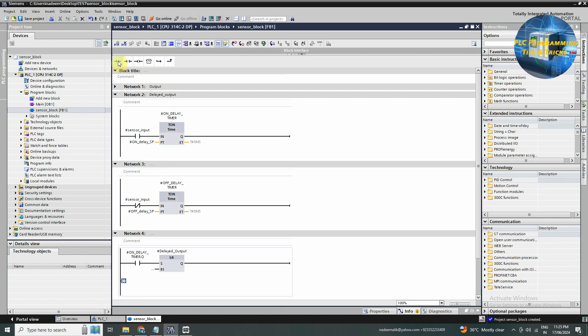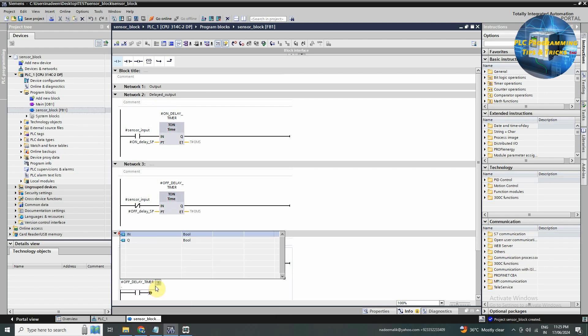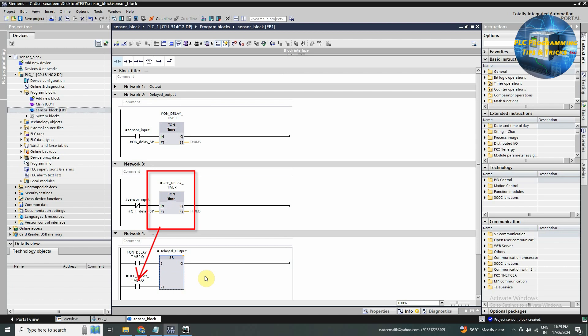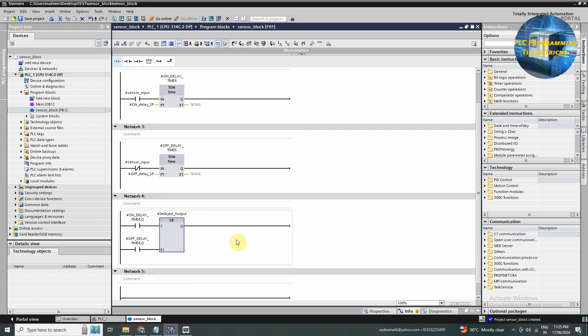Next we will drag and drop a normal open contact at the R or reset input of the SR instruction, and assign the Q output of the off delay timer to this normal open contact. Now as the sensor input turns off, this off delay timer turns on. And once this timer is over, its output Q turns on. And in network four, this contact of the timer closes and resets the delayed output tag. Now the function block for the sensor is ready.